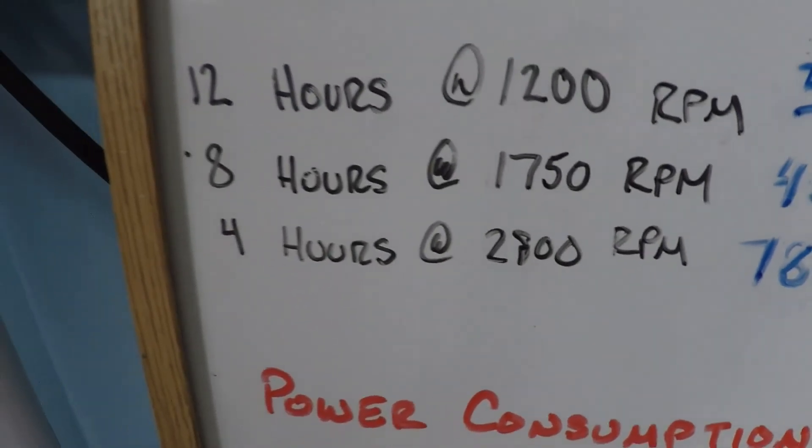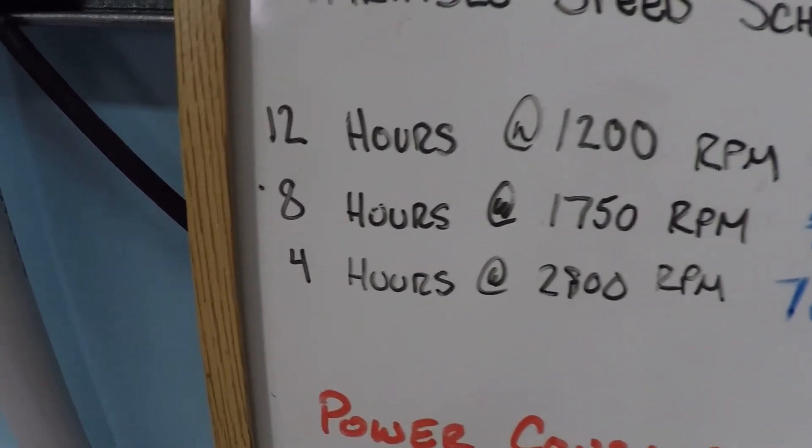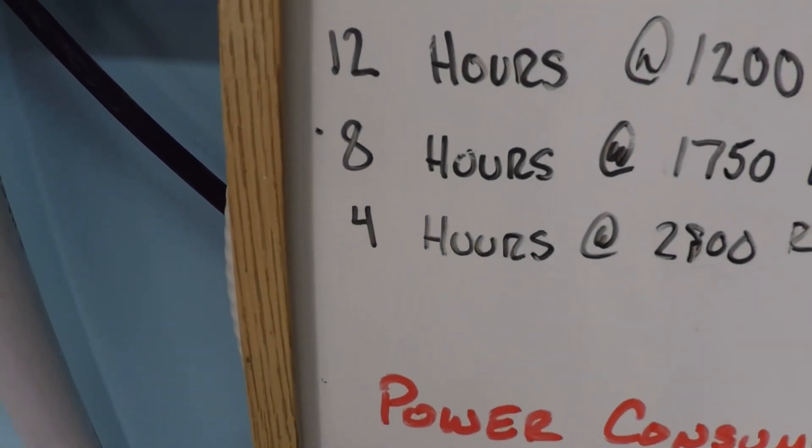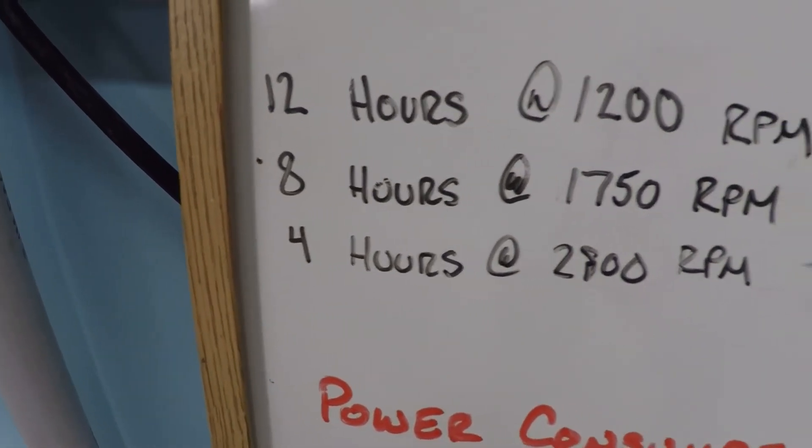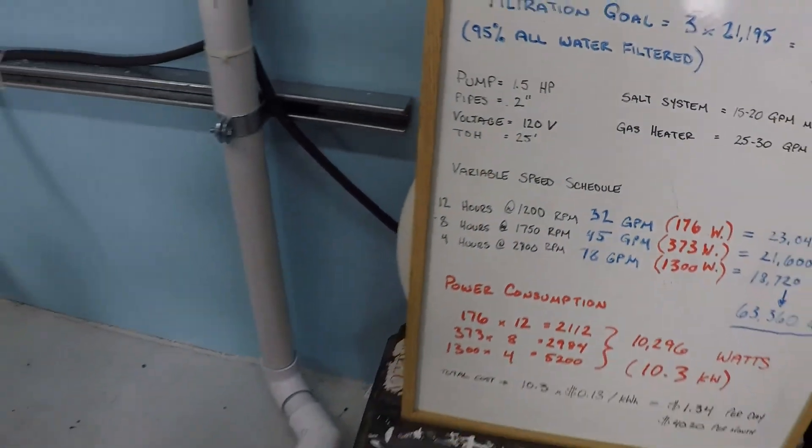And so that's why you see this number at 2800 RPM and not 3000 or 3450. So in this example we're going to have our high periods of time, four hours at 2800 RPM. We should be able to get about 78 gallons per minute.